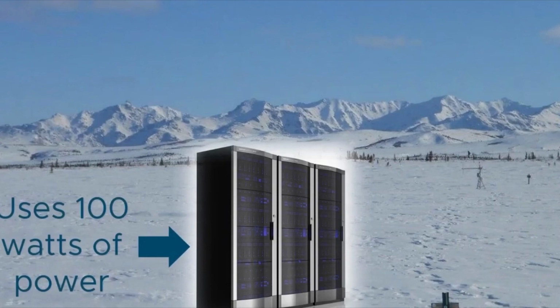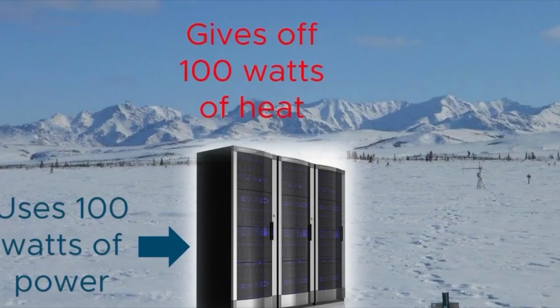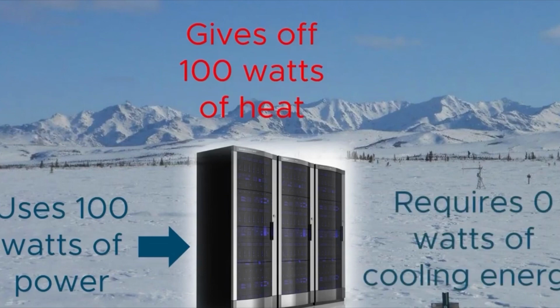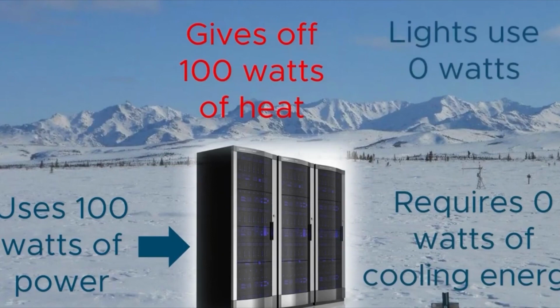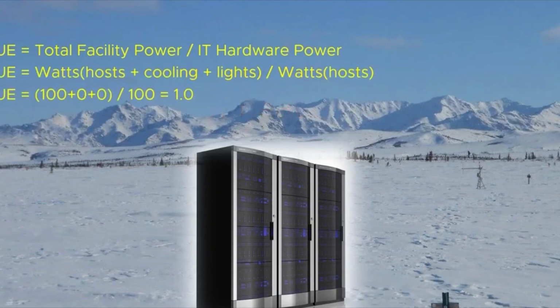Our server is still going to require 100 watts of power to operate, and it will still generate 100 watts of heat. However, because we're using the planet to cool the server, we don't require any additional watts of cooling energy, nor do we require any energy for the lighting. So looking at our example, we now only have 100 plus 0 divided by our 100, which gives us a PUE factor of 1.0, which, by the way, is the lowest a PUE factor can be.